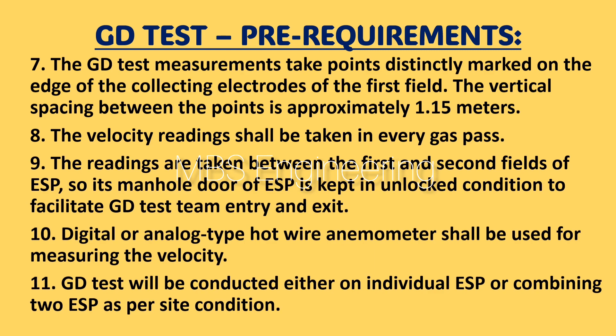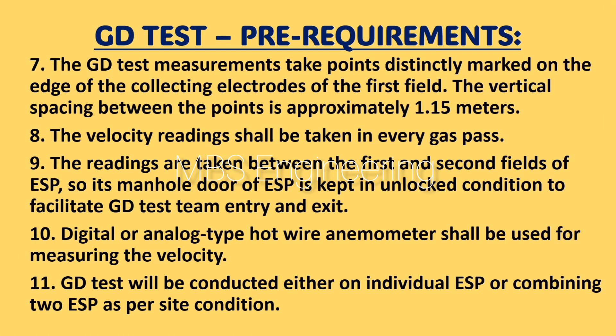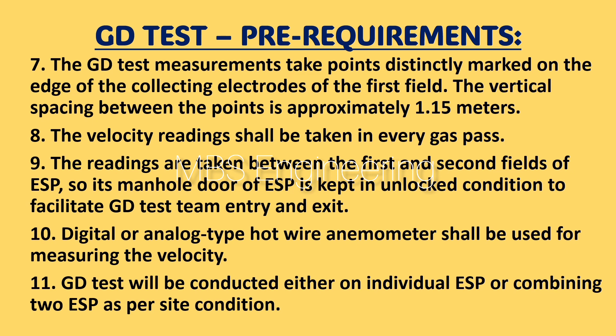Point 9: readings are taken between the first and second fields of the ESP, so the manhole door of the ESP is kept in an unlocked condition to facilitate GD test team entry and exit. Point 10: a digital or analog type hot wire anemometer shall be used for measuring velocity. Point 11: the GD test will be conducted either on individual ESP or combining two ESPs as per site condition.